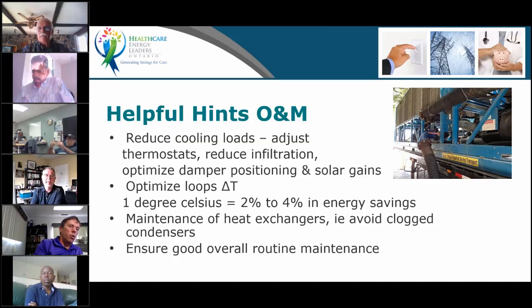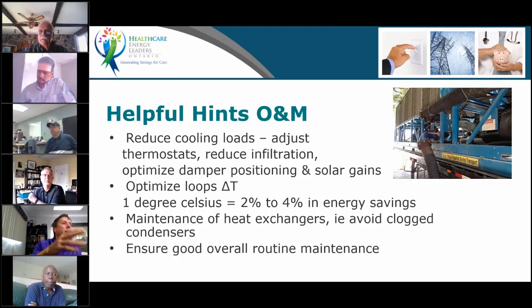Technically, you get more savings per degree C of reset on a constant flow system when it's on the chilled water side. But it is usually more problematic, and you get a little less savings on the condenser side per degree C or per degree F of delta T. It's about 1% per degree F of reset on the condenser, and about 2% on the chilled water side.